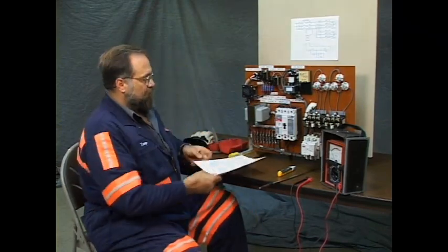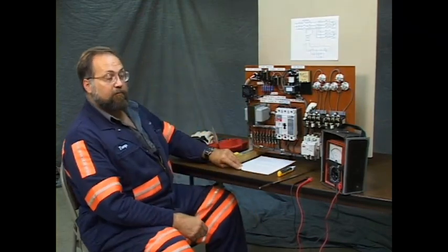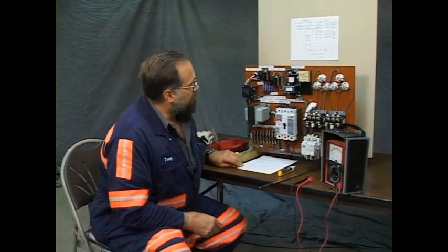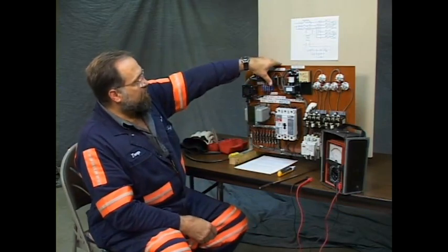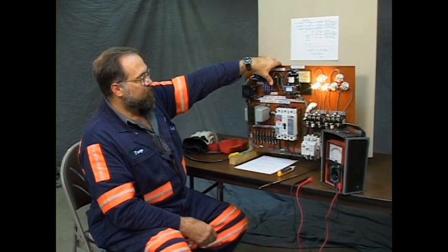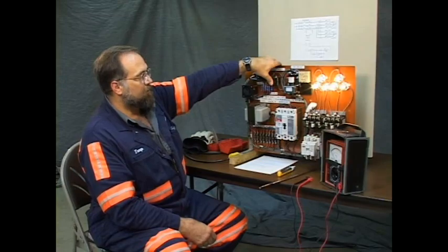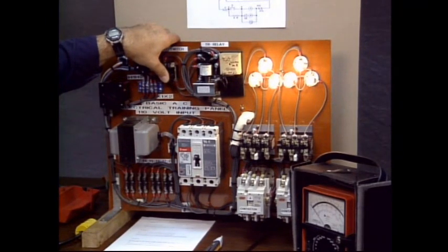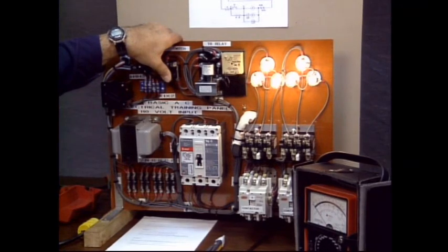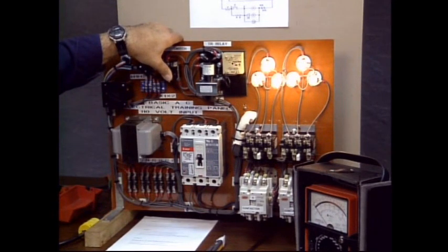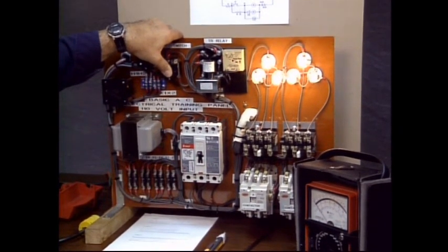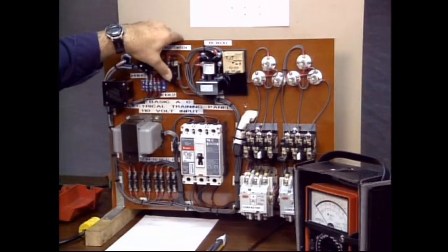Well, I'm glad we have something moving anyway. All the problems prior to this, nothing worked. Let's give this a go. We'll press the start switch. Motor A started first, then after the timed interval, motor B starts. I'm ready to go about my business. I turn loose the start switch though, it quit. That is a problem.